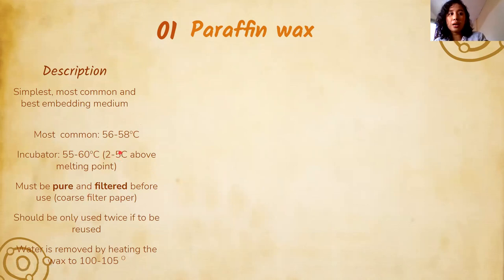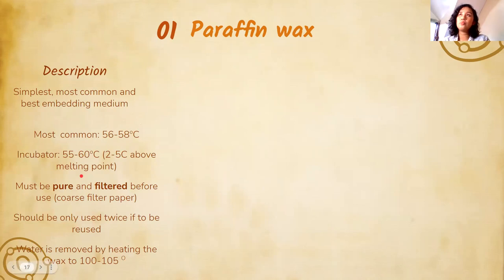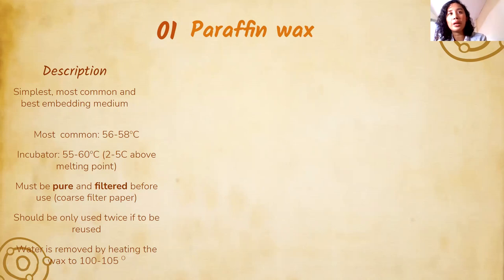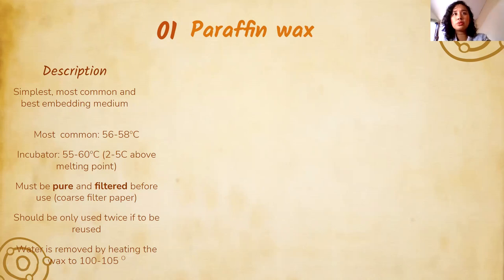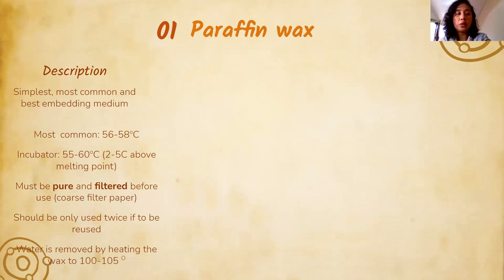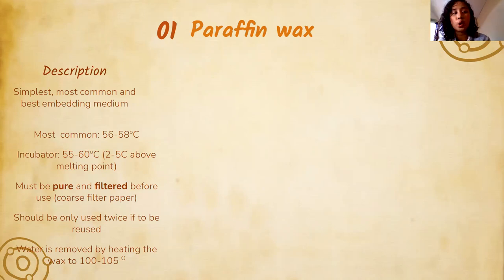Paraffin wax should be pure and filtered before use. It can be reused, but only twice. To ensure a clean, beautiful tissue block without crumbs or dark specks, filter the paraffin with filter paper before use — just like frying oil accumulates crumbs, tissue processing can leave tissue crumbs in the wax. The last change of paraffin should be clean. The paraffin used for embedding from the dispenser should never have been used before.